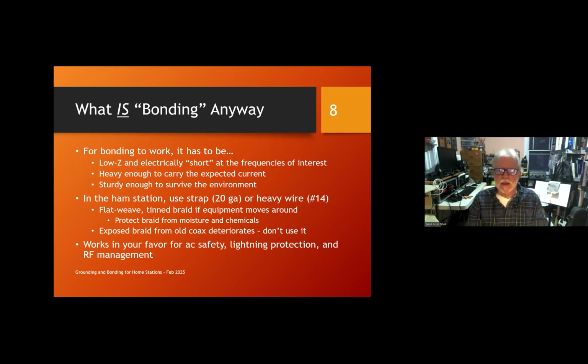That's why the spec calls for number 6, number 4, number 2, lots of copper. It's heavy enough to carry the expected current without vaporizing. If you use a small wire, it may do the job for a while, but if it gets hit with a big surge of current, it'll make a nice green lightning bolt, and suddenly you won't have a wire anymore.